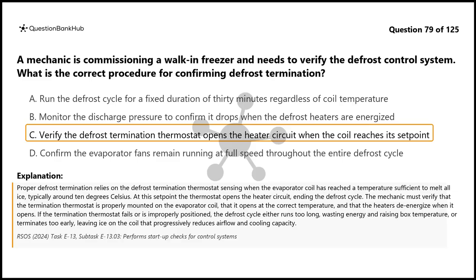The mechanic must verify that the termination thermostat is properly mounted on the evaporator coil, that it opens at the correct temperature, and that the heaters de-energize when it opens. If the termination thermostat fails or is improperly positioned, the defrost cycle either runs too long, wasting energy and raising box temperature, or terminates too early, leaving ice on the coil that progressively reduces airflow and cooling capacity.